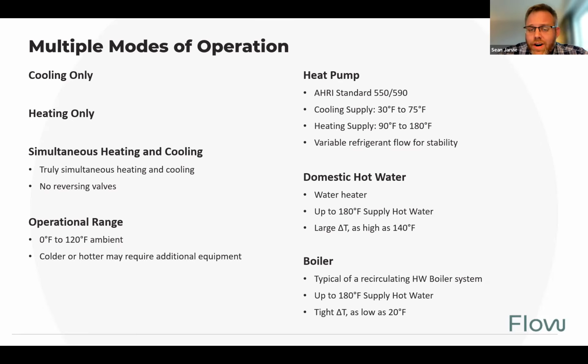Now, domestic hot water heating is definitely new and a novel case for CO2 as a refrigerant. And there are a few companies that are coming on board with this now. Any domestic hot water heating system really needs a very high delta T to make everything work. And so you need that 100 to 150 degree delta T to make domestic hot water heating work, but it can do up to that 180 degree water. Most of them are about 140 degrees.